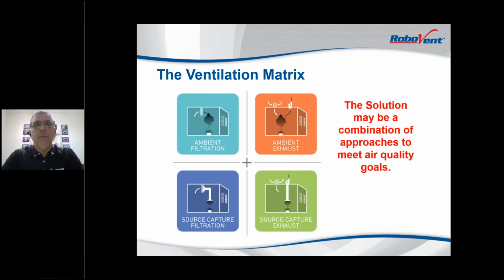The other side is ambient exhaust, up on the top right, and that's simply connecting a fan or an exhaust system and capturing the air in the area, not at the source, and just blowing it outside. The bottom right, excuse me, is a hybrid of that. Instead of just capturing air from the manufacturing space, connect it right to the machine and do not filter it, but just blow that outside. The issue with ambient exhaust or source capture exhaust, not filtering it, is you're dumping that air outside. If you're in the northern part of the US where it gets cold, or in the south where it gets hot, that may require some heating. You're pulling air in from somewhere else that's cold if you're doing ambient exhaust, or exhausting the air without filtering it and returning that filtered air to the plant. You're going to have increased HVAC or heating and ventilating cost as you pull that cold or hot air from the outside.